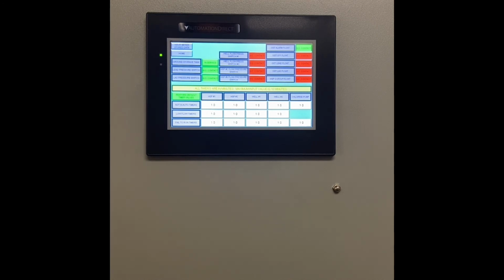Those mechanical components will have to be configured manually by the operator, and then placing the system in the appropriate operational mode, whether it be groundwater storage tank in service or bypassed. Now at the bottom we have some failure modes and some timers. So on the left you'll see not in auto timers, low flow timers, and fail to run timers. And we move from left to right and you'll see high service pump 1, 2, wells 1 and 2, and the chlorine pump, and there is a number associated with each one.